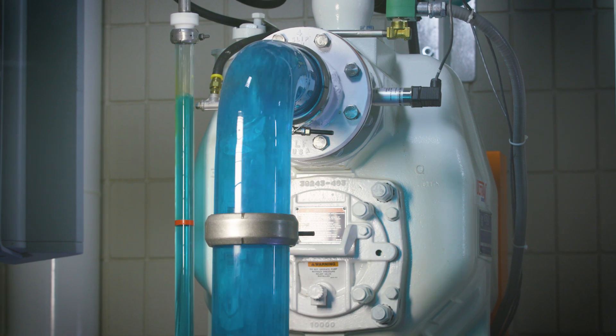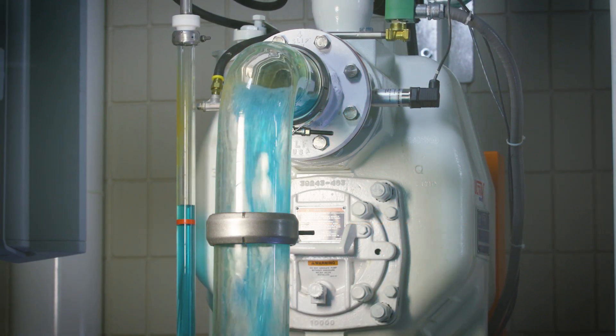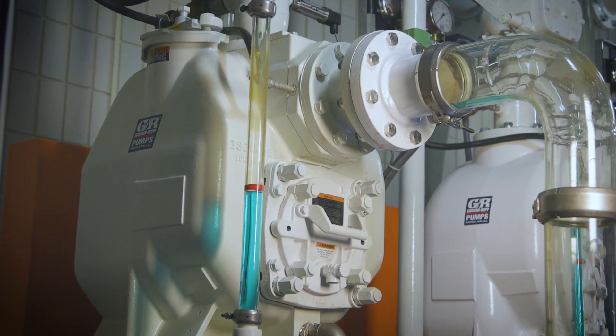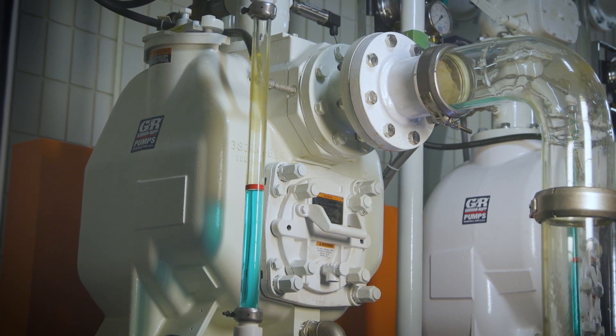To simulate this, the demonstration pump is shut off, causing the water to drop down the suction pipe. With that, an additional amount of water is siphoned out of the pump casing, causing the water inside the pump to fall to a level that requires a re-prime.